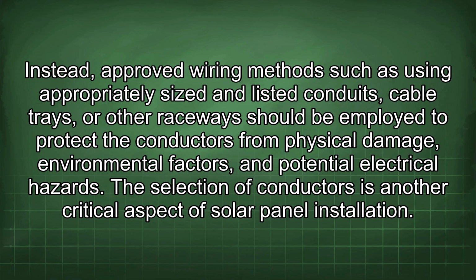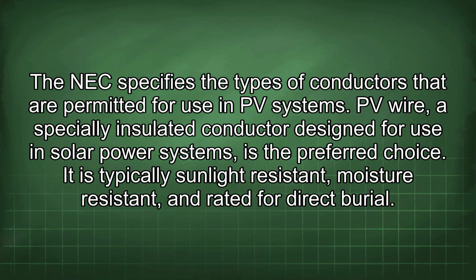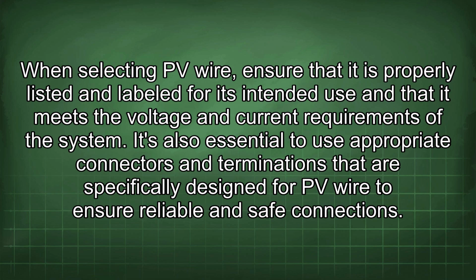The selection of conductors is another critical aspect of solar panel installation. The NEC specifies the types of conductors that are permitted for use in PV systems. PV wire, a specially insulated conductor designed for use in solar power systems, is the preferred choice. It is typically sunlight resistant, moisture resistant, and rated for direct burial. When selecting PV wire, ensure that it is properly listed and labeled for its intended use and that it meets the voltage and current requirements of the system. It's also essential to use appropriate connectors and terminations that are specifically designed for PV wire to ensure reliable and safe connections.